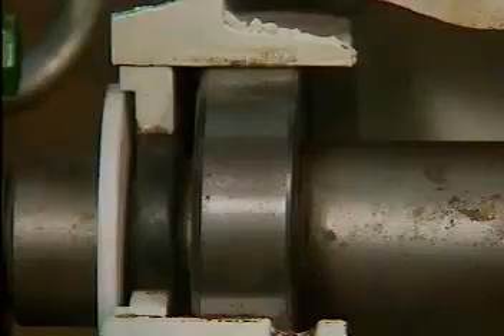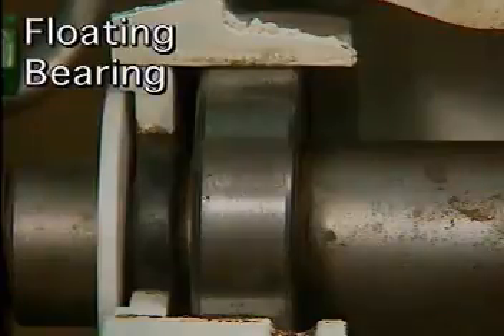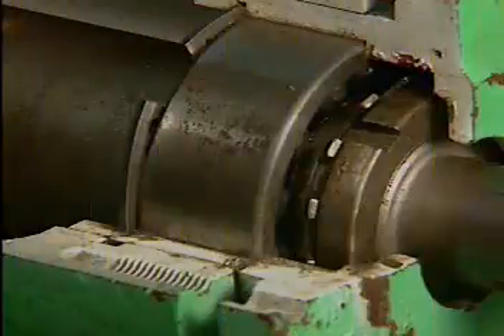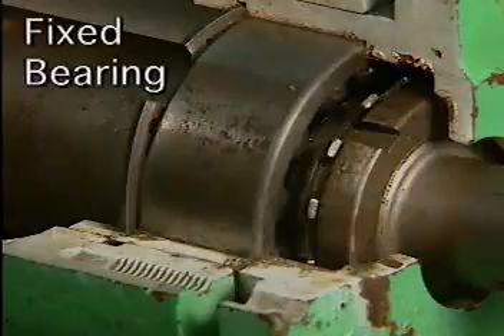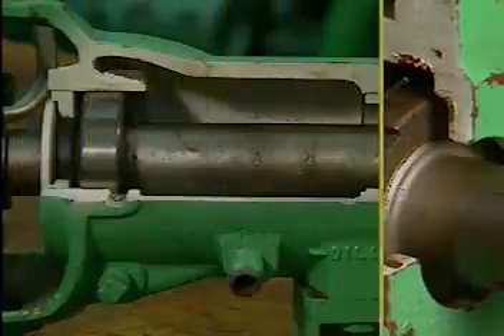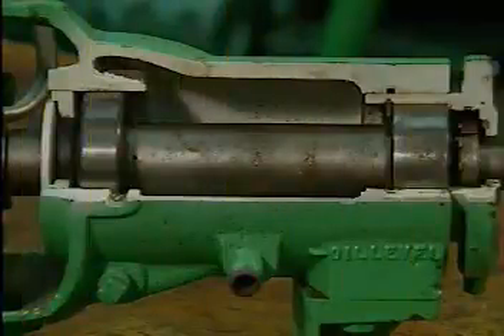worked on. Bearing housings can be built either to allow a small amount of axial movement or to completely prevent axial movement. A housing that allows a small amount of axial movement is said to have a floating bearing. A housing that prevents all axial movement is said to have a fixed bearing. Both types of housings may be in the same machine.